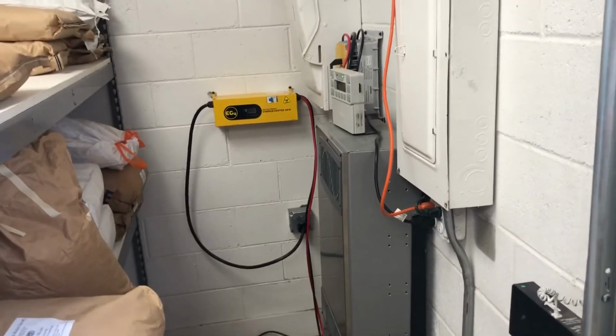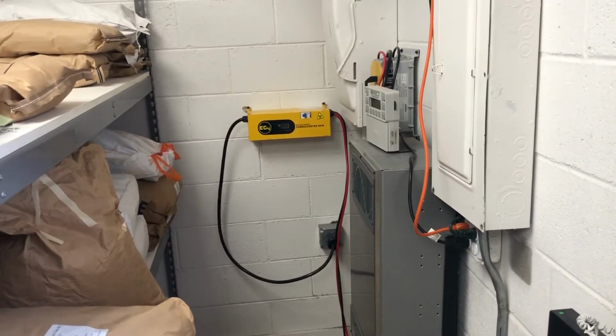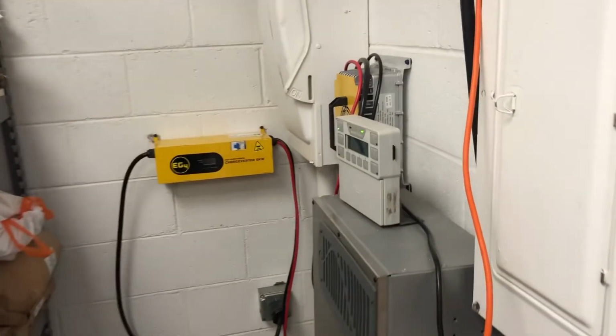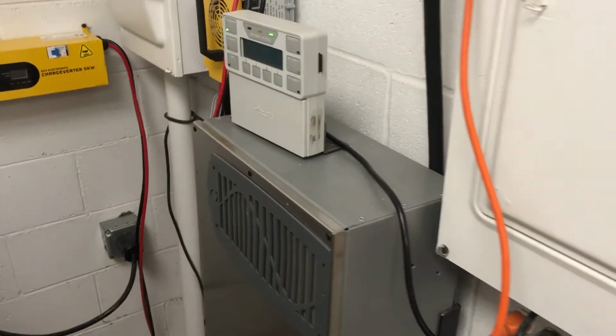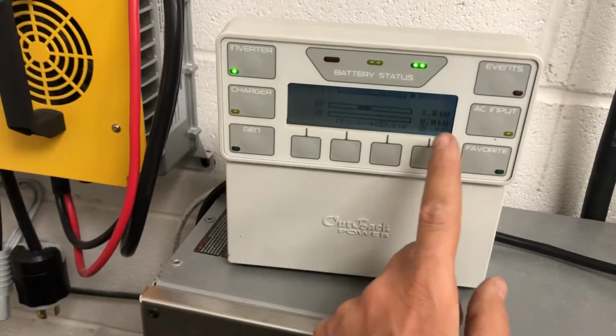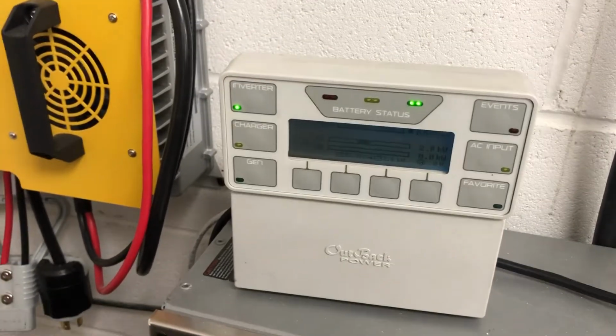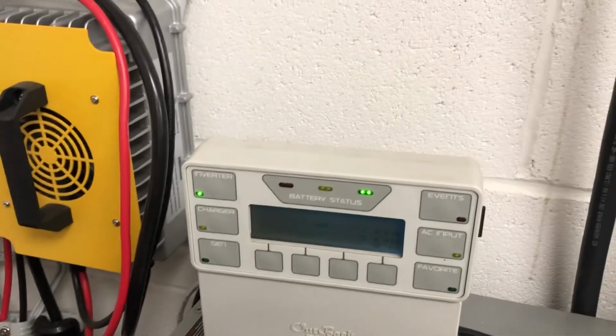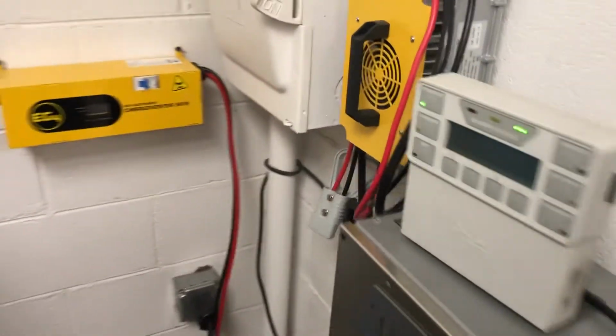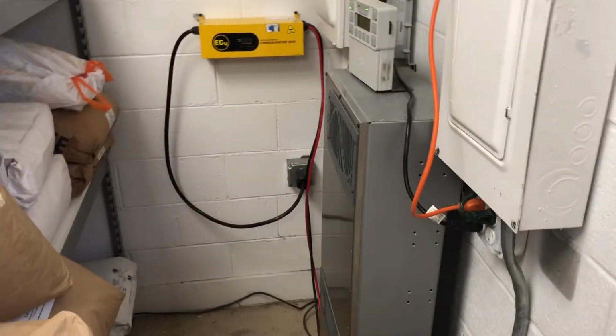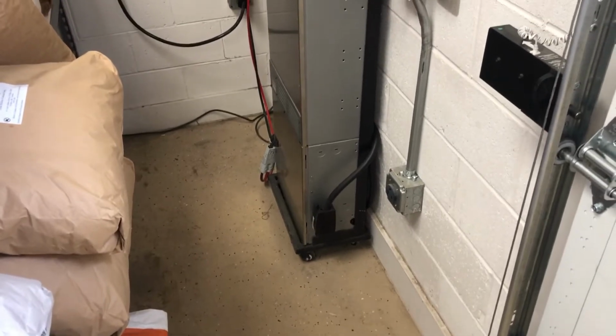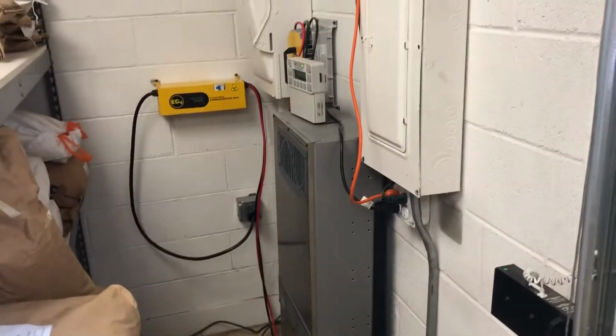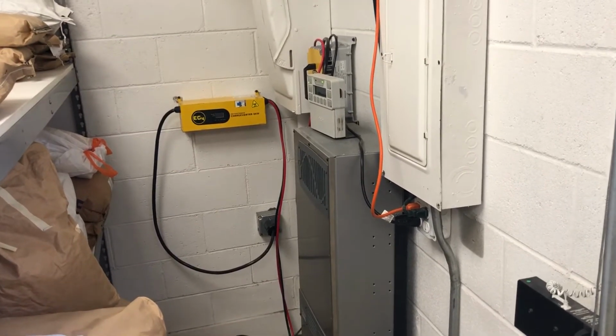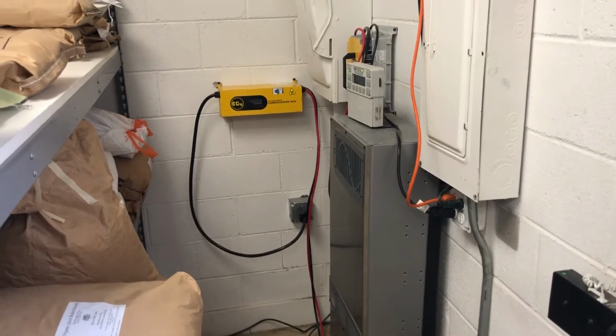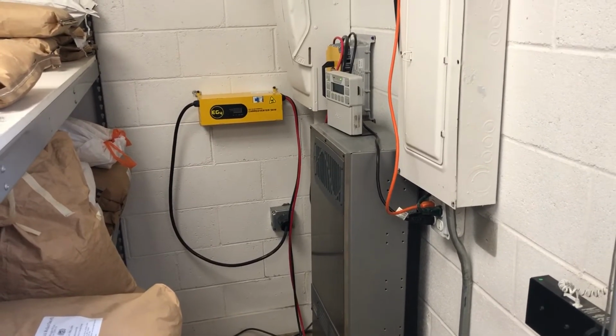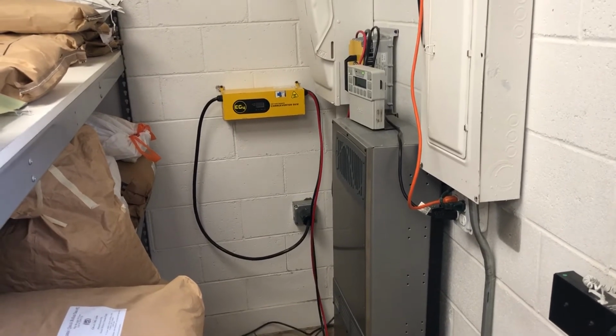It's a super great application of the low current phantom draw from a low capacity AC input, but a system that can handle larger outputs. When the air conditioning was running, we were up at about 4.5 kilowatts, and the batteries have been maintaining a really high, full state of charge for months now. But those 4 batteries can handle peak loads. So that's the system, and it's been working really well, and it has gotten the diesel generator shut down, which was my main goal. And so I'm really proud of that. So I hope that was cool. Kind of an interesting application of a low current grid connection using this charger.